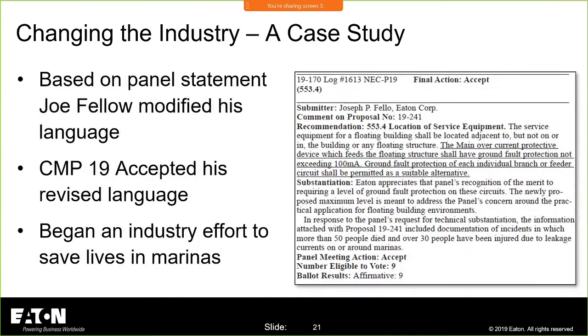So what we went back with was, we did some homework. We looked at everybody who made ground fault protection of equipment, and nobody made GFPE with greater than 100 milliamp leakage current capability. So then we proposed this: the main overcurrent protective device feeding the floating structure shall have ground fault protection not exceeding 100 milliamps, and ground fault protection of each individual branch circuit shall be permitted as a suitable alternative. It was accepted—9 people on the panel, 9 voted affirmative.